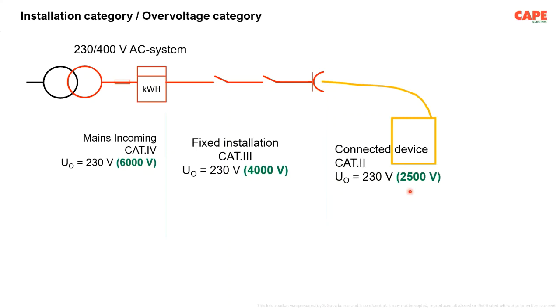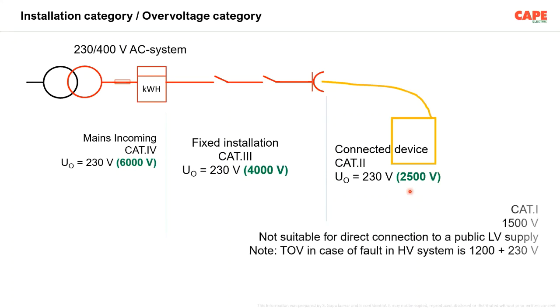What this means is, in the electrical installation, we are going to have some big equipment, we are going to have some medium size equipment, we are going to have a little bit smaller equipment with respect to its insulation. We are going to also have sensitive electronic equipment. The sensitive electronic equipment comes under category 1. For example, a surge voltage of 1500 volt.